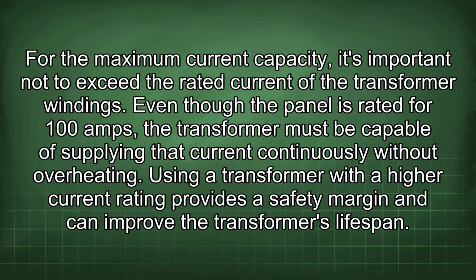For the maximum current capacity, it's important not to exceed the rated current of the transformer windings. Even though the panel is rated for 100 amps, the transformer must be capable of supplying that current continuously without overheating. Using a transformer with a higher current rating provides a safety margin and can improve the transformer's lifespan.